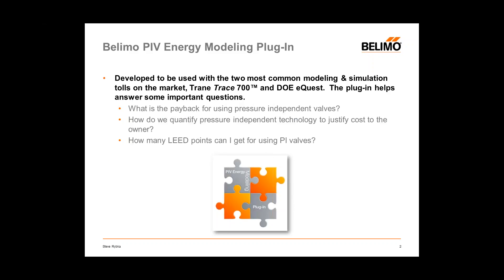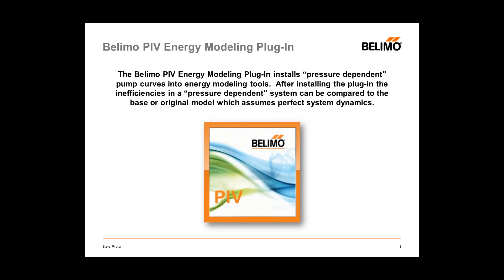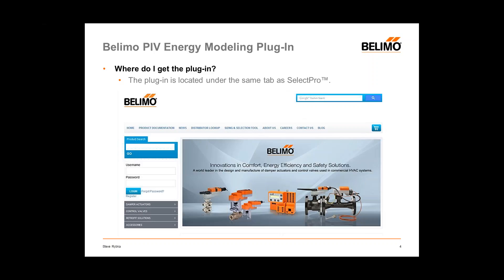The pressure independent valve plug-in was developed to work with TRACE 700 and eQuest, and it is intended to help qualify the use of pressure independent valves within a building or control system. The Belimo pressure independent valve energy modeling plug-in installs pressure-dependent pump curves into energy modeling tools. Once the plug-in is installed, the inefficiencies of pressure-dependent systems can be compared to the base or original model, which assumed perfect system dynamics.